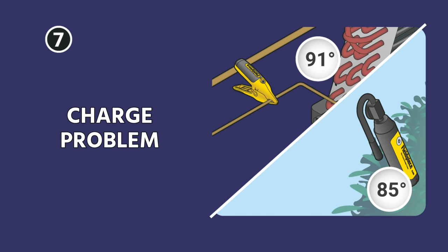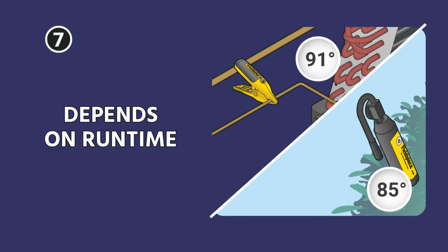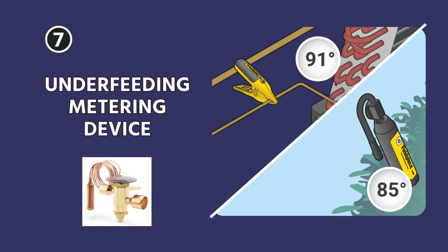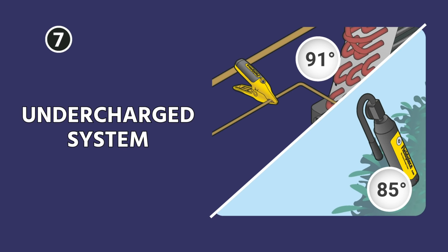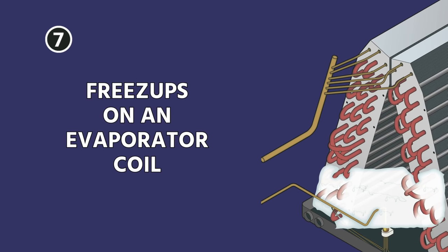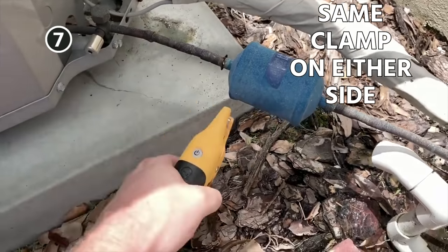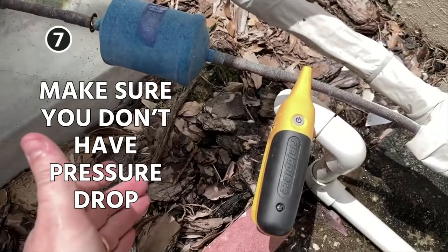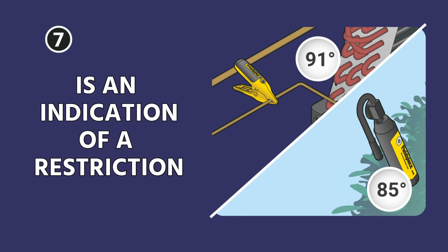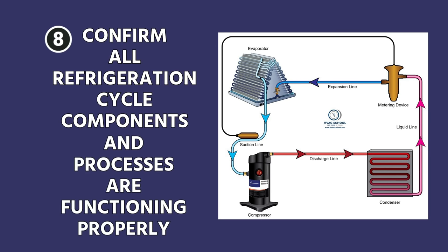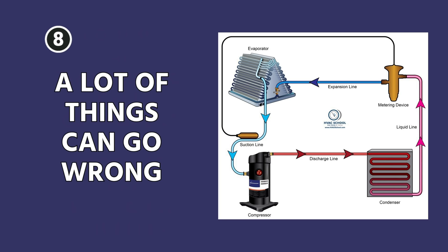A lot of folks will say that a charge problem or a restriction in the liquid line won't cause freezing. It really does depend on runtime, the market you're in, and how much moisture is in the air. But there are certainly cases where restrictions — whether it's an underfeeding metering device, a restricted liquid line dryer, or a system that's just plain undercharged — can cause freeze-ups on an evaporator coil. In terms of liquid line filter dryers, use the same clamp on either side and make sure you do not have a temperature drop across it. Anything measurable over one degree is an indication of a restriction in most applications.